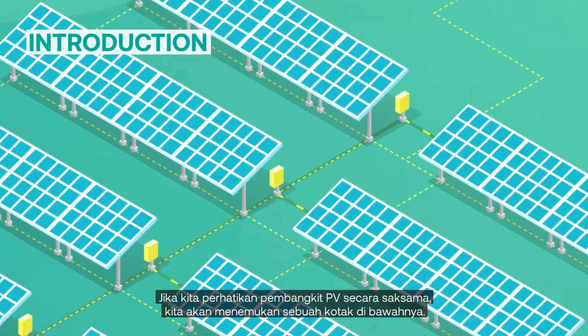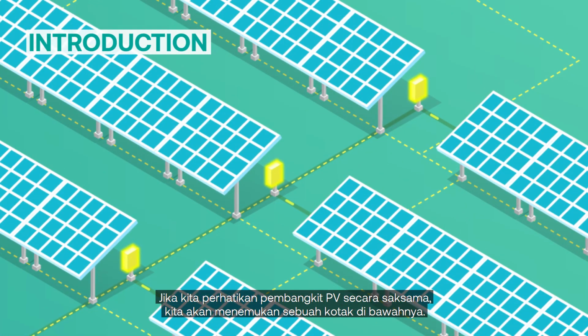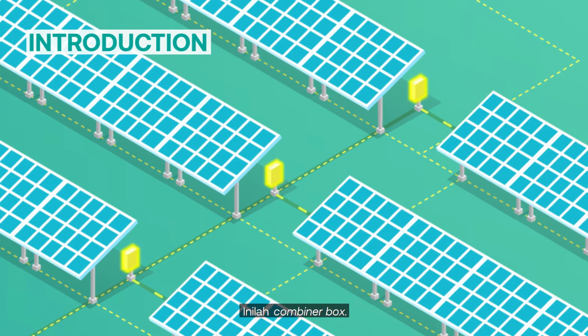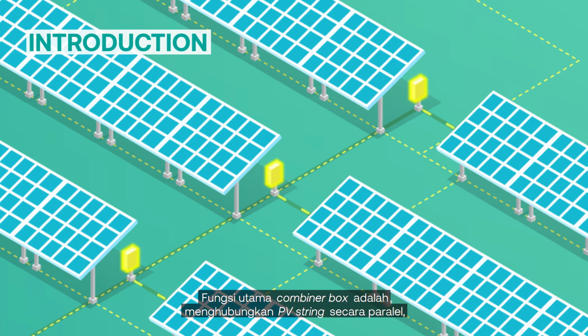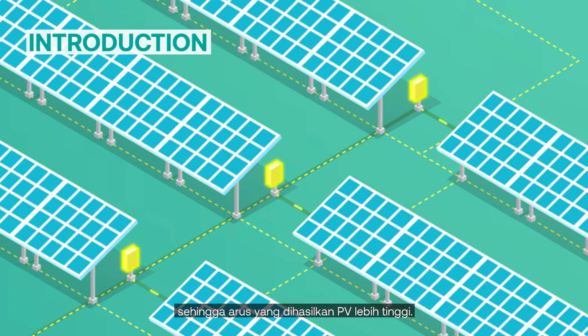If we observe a PV power plant closely, we will find a box under some PV modules. This is the combiner box. So what is a combiner box? Series connected PV modules are called a PV string.